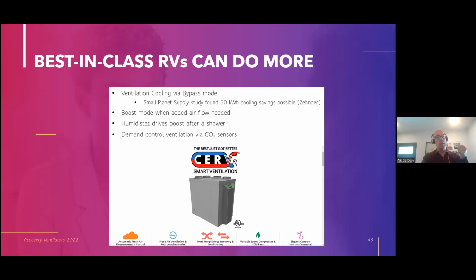Other systems like my ADU one has a humidistat driving a boost. Others have manual boost mode. And then ventilation cooling via bypass mode. As part of our best-in-class study, which you'll see if you look at the study, we tested what would happen if an HRV monitoring outdoor air temperature would shift to 100% outdoor air when that was favorable to the energy balance. That is, don't exchange the air from the inside when it's not favorable. Just bring the outside air in when it's nice and cool, like a whole house fan does, right? And we found in climate zone 5, 50 kilowatt hours additional possible for that function like those Zehnders have. So that's a good feature to look for, especially in mild climate zones.